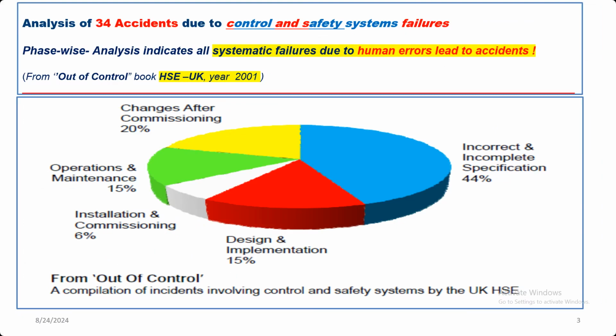So the second level of failure was at 20%, which came after changes following the commissioning of the plant. I have observed in many industries that the P&ID given at the time of installation of the plant is hardly addressed later on. But you do a lot of changes later on to suit either production or safety or quality, for many reasons. But no P&ID gets revised. As a result, in the long term, the person who is attending the plant 10 years after its erection doesn't get the clue. And if he makes changes which are not recorded, that means the management of change system, known as MOC, is not being followed, and that can lead to accidents. This is as per the survey that has been done.